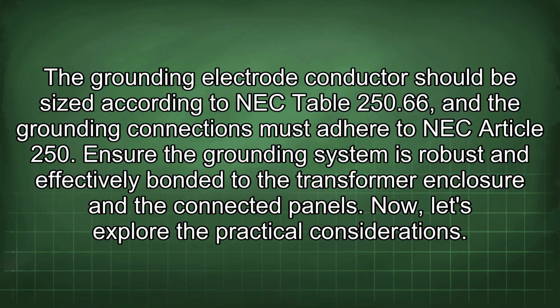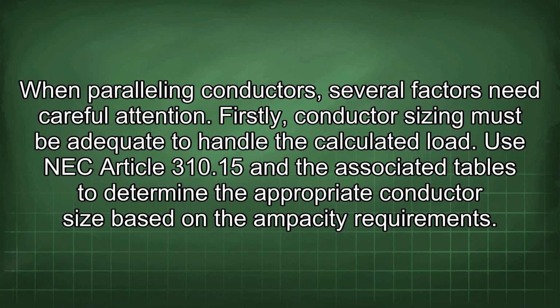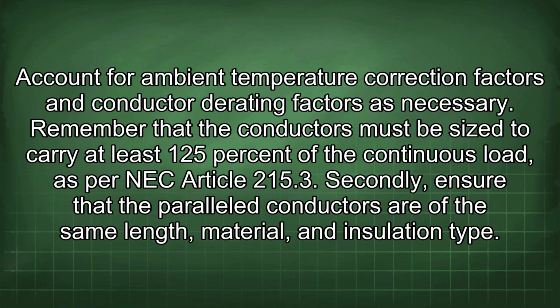Now let's explore the practical considerations. When paralleling conductors, several factors need careful attention. Firstly, conductor sizing must be adequate to handle the calculated load. Use NEC Article 310.15 and the associated tables to determine the appropriate conductor size based on the ampacity requirements. Account for ambient temperature correction factors and conductor derating factors as necessary. Remember that the conductors must be sized to carry at least 125% of the continuous load as per NEC Article 215.3. Secondly, ensure that the paralleled conductors are of the same length, material, and insulation type.